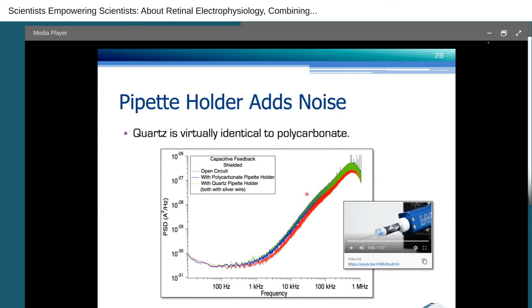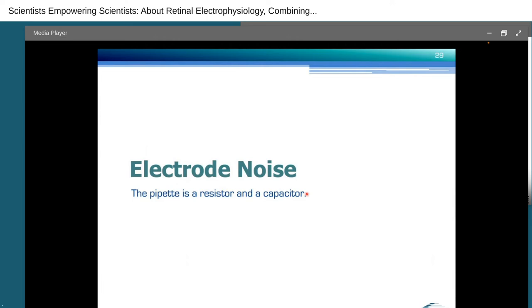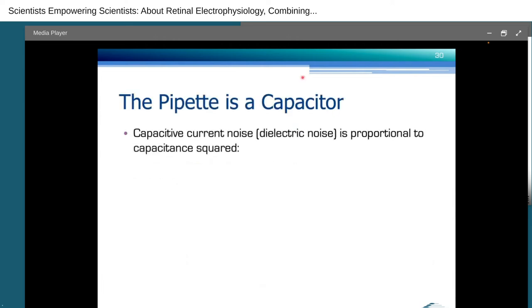I wanted to investigate the pipette holder. The pipette holder went in the shielded box as well. What happens is it doesn't really add that much noise. The Axon guide says it's about 10%. It looks like it's less than that, but it's across the entire spectrum. With the polycarbonate pipette holder, we also make quartz holders. This superimposed now in green is virtually identical to the polycarbonate holder. Not too surprising since the whole thing is in air. So the material, the dielectric constant, we'll get to that in a second, does not play that big of a role. The quartz pipette holder is important for mechanical stability. In terms of noise performance, it doesn't do a whole lot. Let's take a look at electrode noise. The electrode is both a resistor and a capacitor.